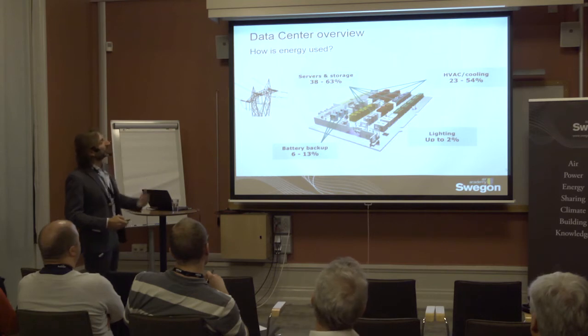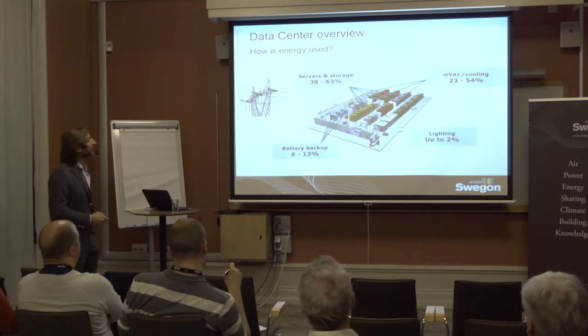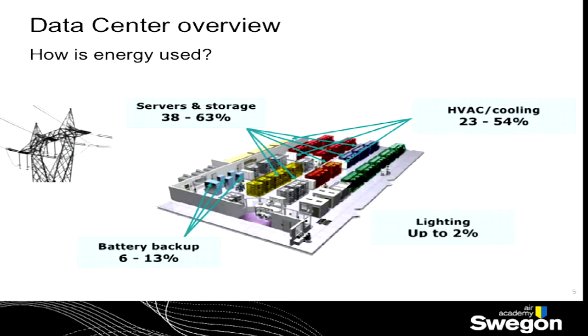But how is it used? For sure, some of my colleagues went into this discussion before, but we can roughly say that the HVAC and cooling consume about, let's say, 30 to 40% of the total energy introduced into a data center. 6 to 13% is for the battery and backup. Lighting is maximum up to 2%. And the rest of the energy introduced is used for the main purpose of a data center, so for the server and storage.